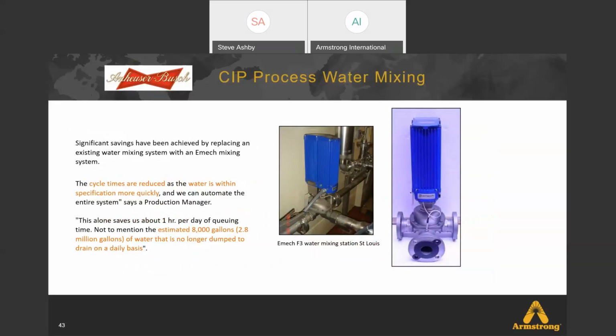The CIP water savings in this application were pretty impressive. Significant savings have been achieved by replacing an existing water mixing system with an Emech mixing valve. The cycle times were reduced, and the water is within specification more quickly. So we've talked about that: get to the temperature fast and hold it. They're able to automate the entire system, and the water savings were pretty significant. If you take a look there, it's estimated at 8,000 gallons, 2.8 million gallons of water that is no longer dumped to the drain on a daily basis.